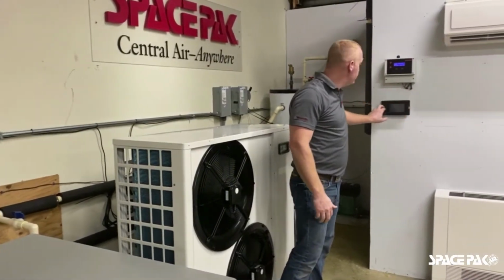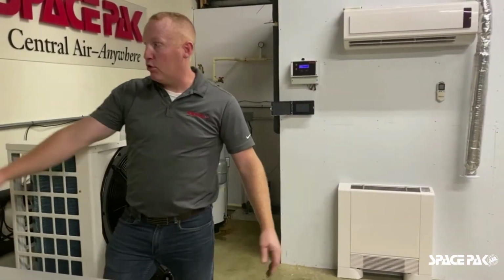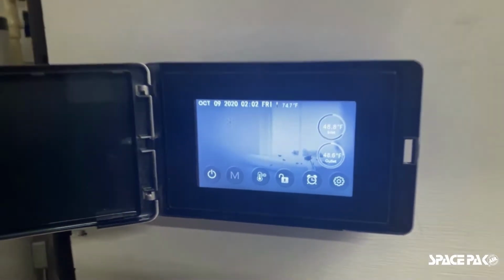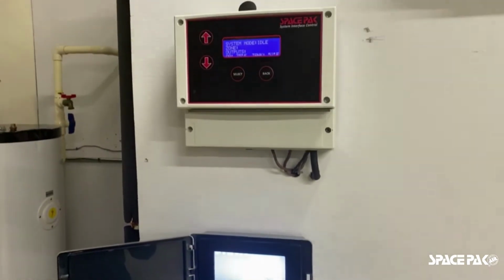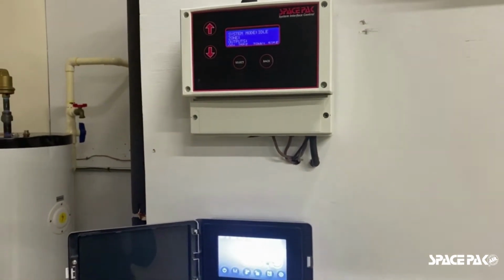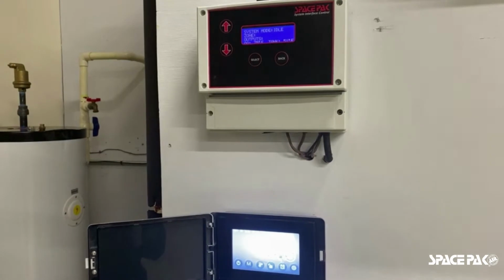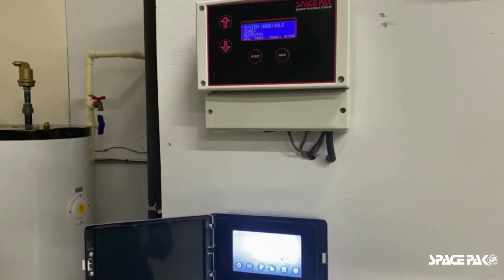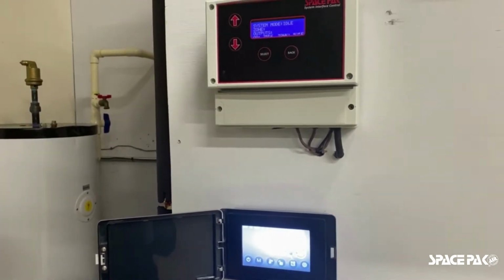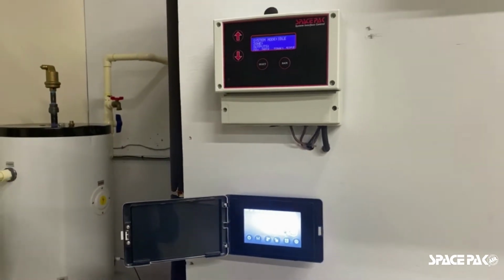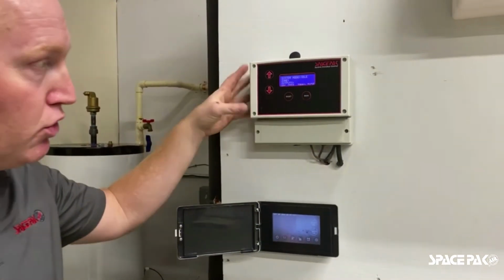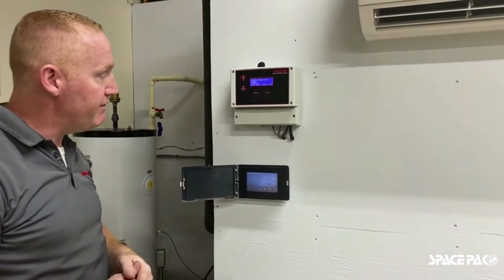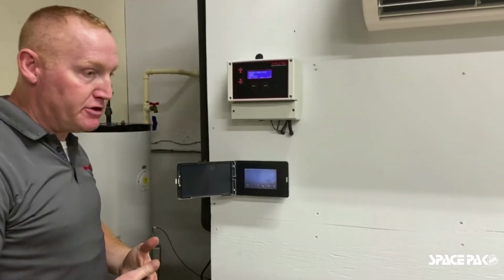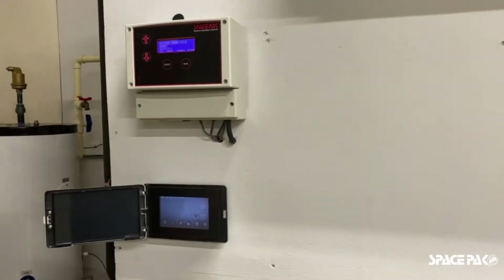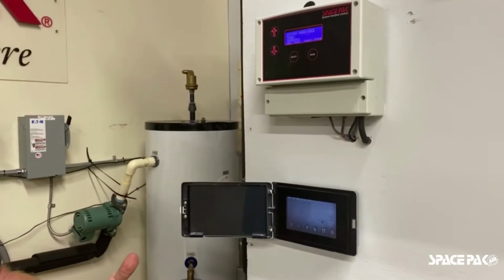We've remotely mounted the actual control for the unit. So one thing to keep in mind, when this control is in a black and white screen, it means there is no call coming in. There's no heating call or cooling call coming into the system. Okay, we have our systems here hooked up to the SpacePak system interface control, or the SSIC control, if you will. We're going to enable the buffer tank for this unit. So in enabling the buffer tank, it'll allow us to maintain a buffer tank temperature.